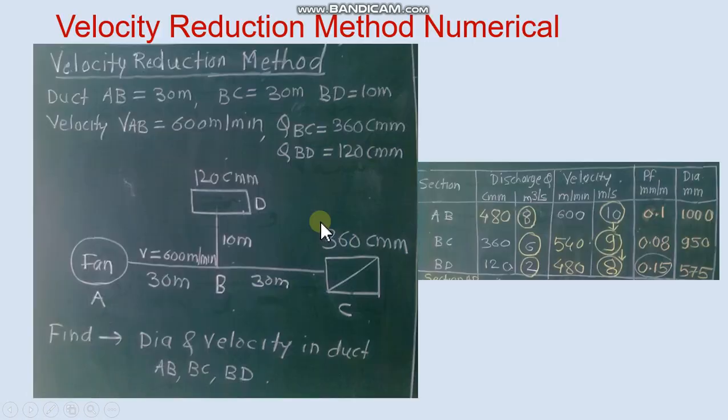Now in second section we assume velocity in decreasing manner. So in second section we assume velocity 9 and third section we assume velocity 8. So we obtain for the value of this velocity and corresponding discharge PF and diameter. Similarly we obtain for this velocity and discharge PF and diameter from friction chart.